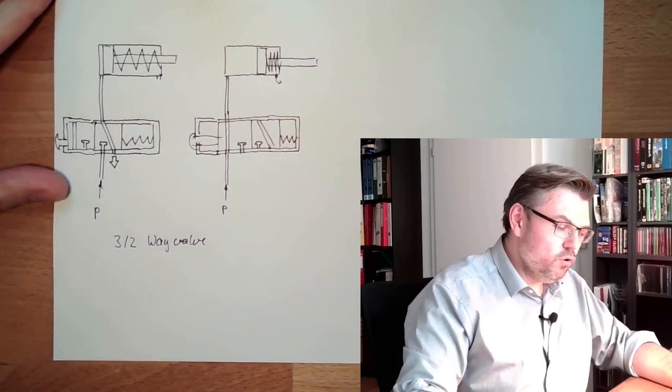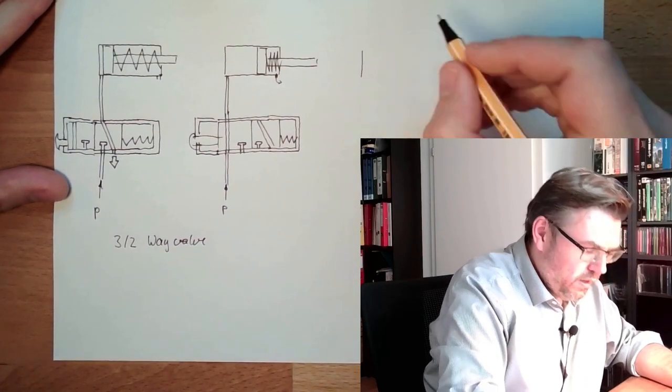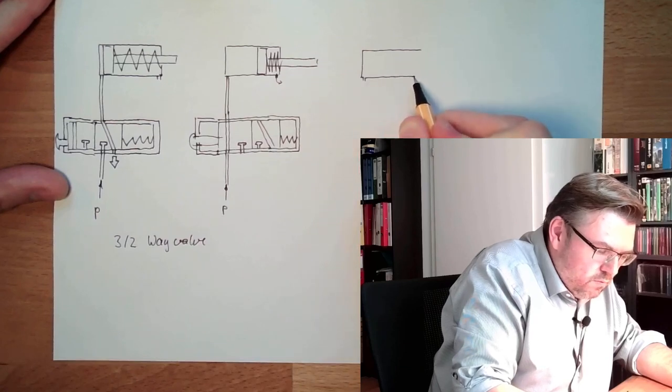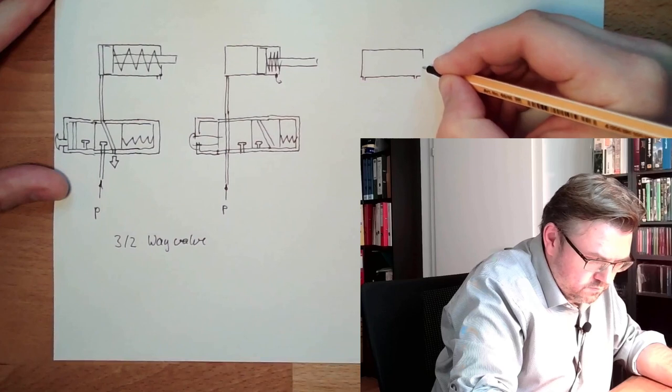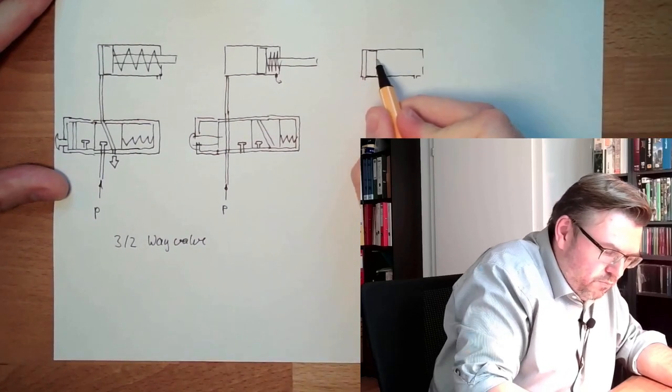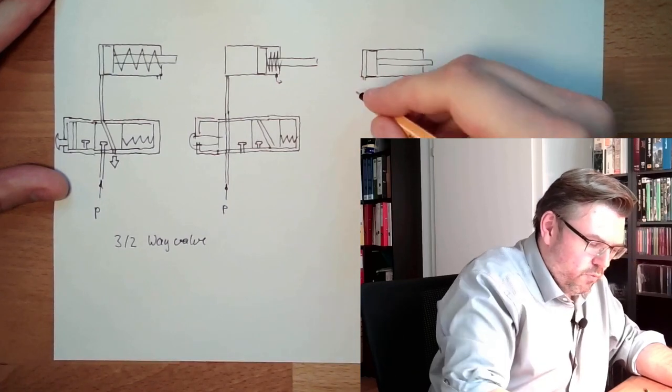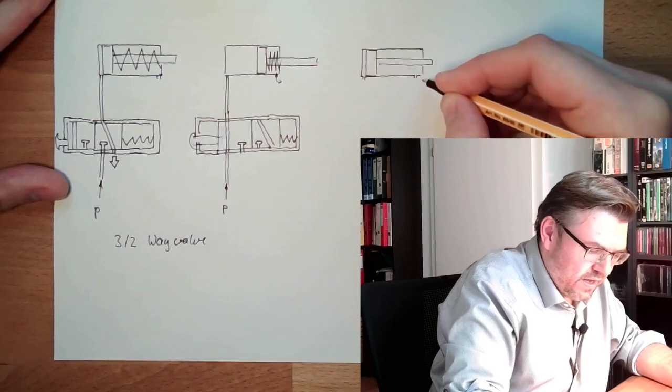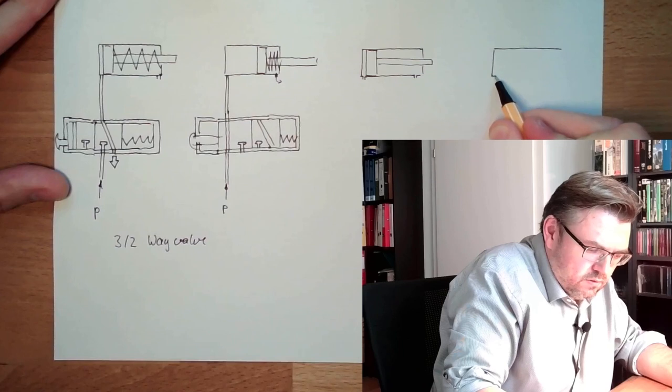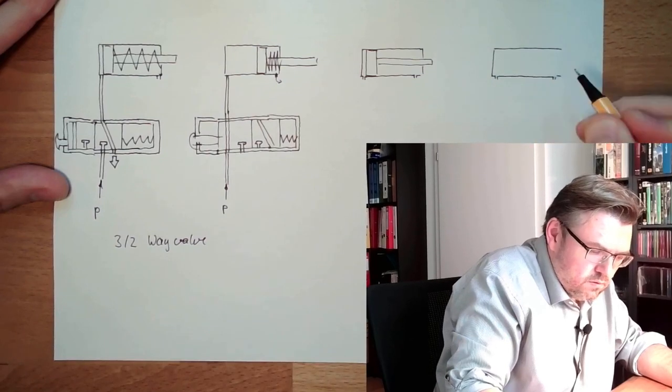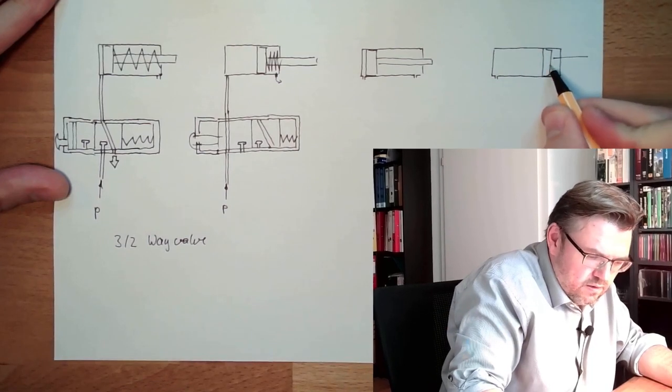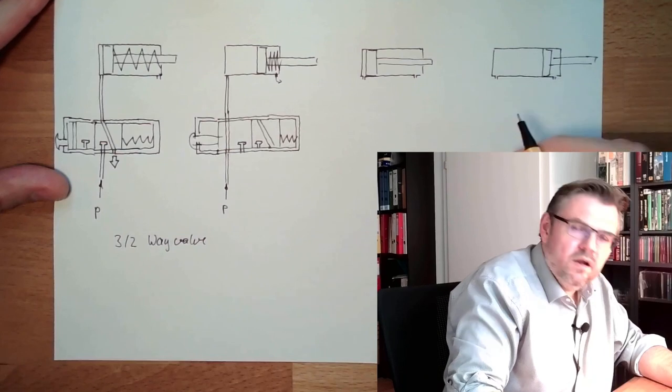Let's see how it would look like for a double-acting cylinder. Well, if we have a double-acting cylinder, we have two connections here. One, two. If we want to have it on the left-hand side, so the piston rod is inside, we have to exhaust this and put pressure here. If we want to have it exactly the other way around, so that the piston is on the right-hand side, we have to put pressure here and exhaust here.